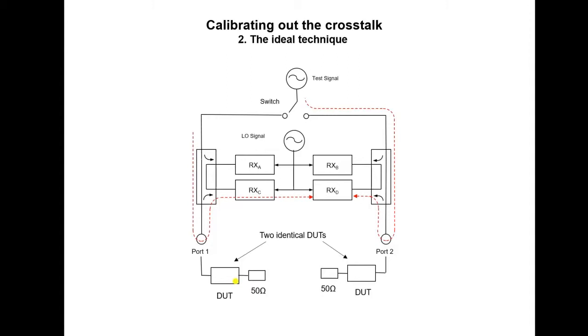The idea is that the impedance, or return loss you present to ports 1 and 2 during calibration, is the same as during the measurement. The idea can work very well, but it is not always practical to have two identical DUTs.